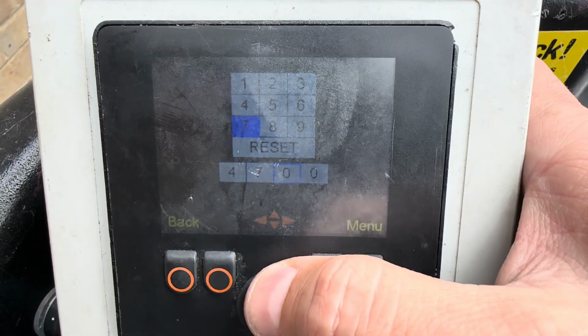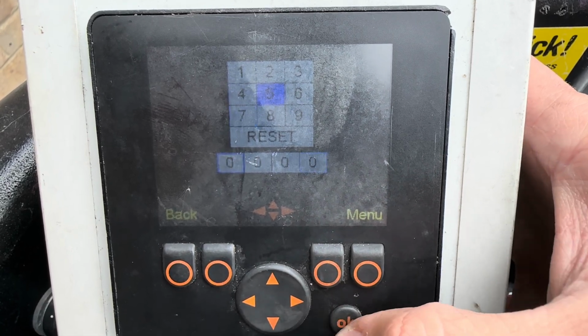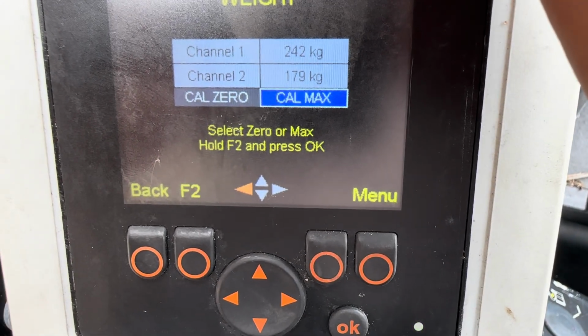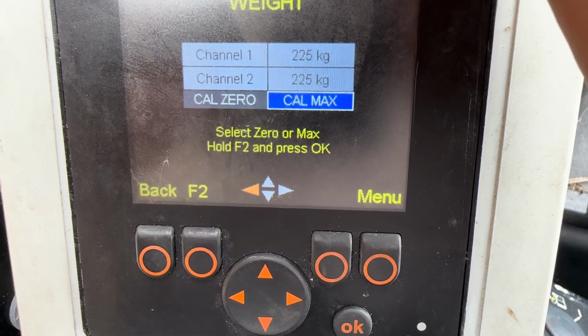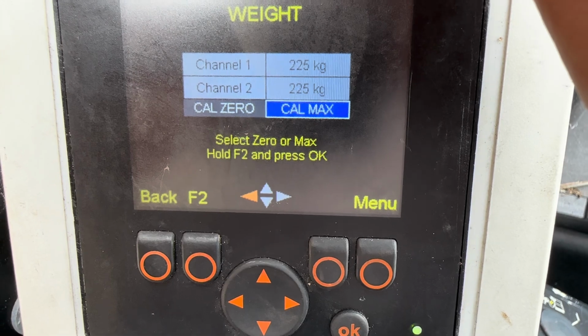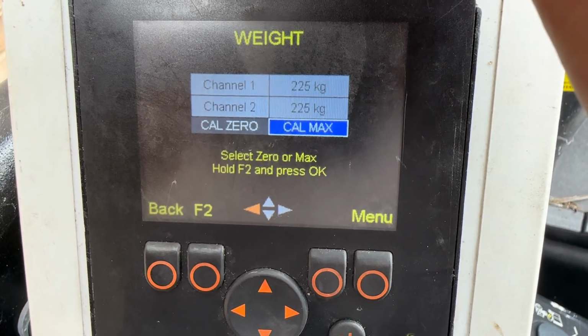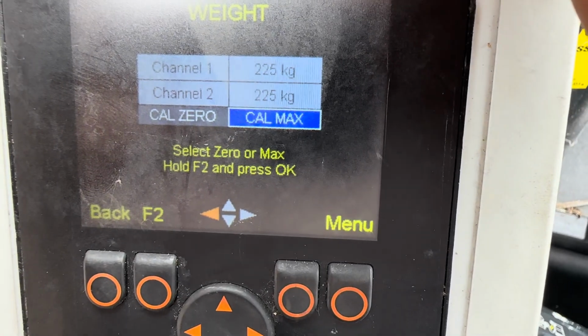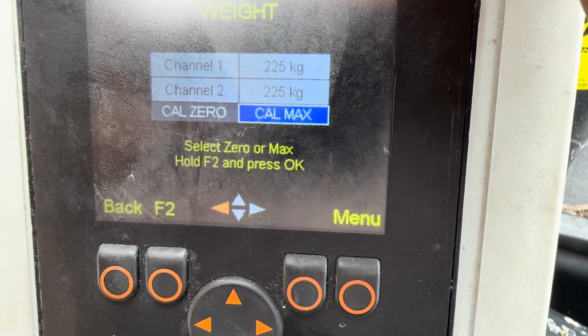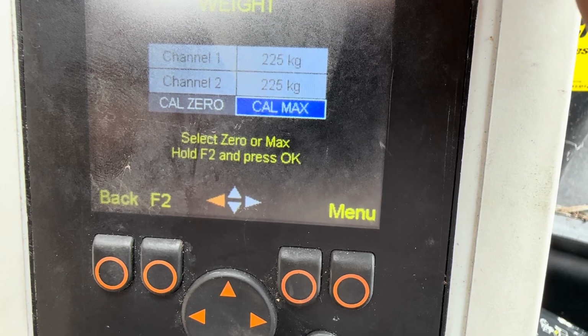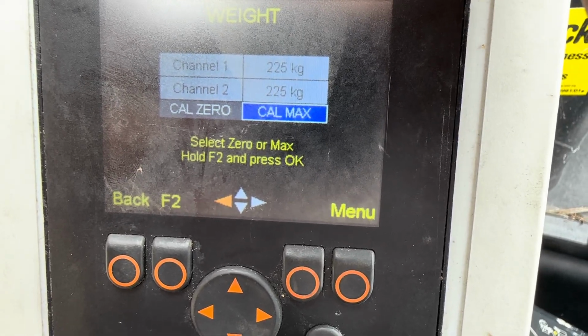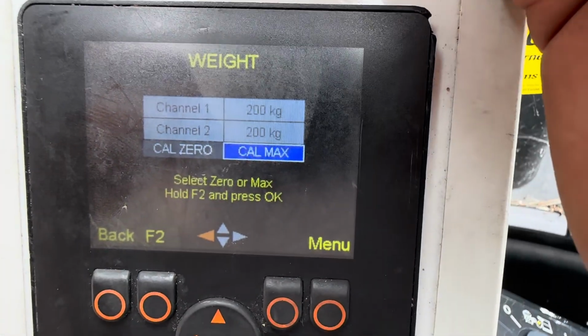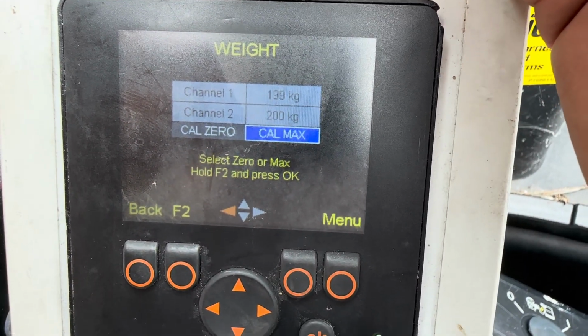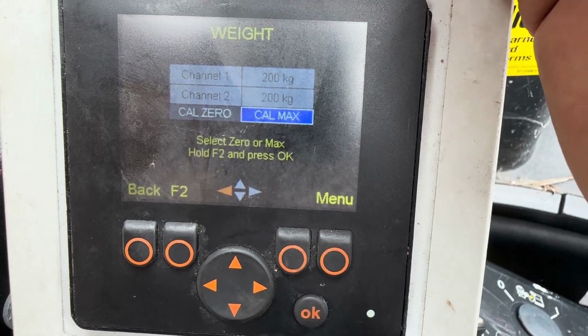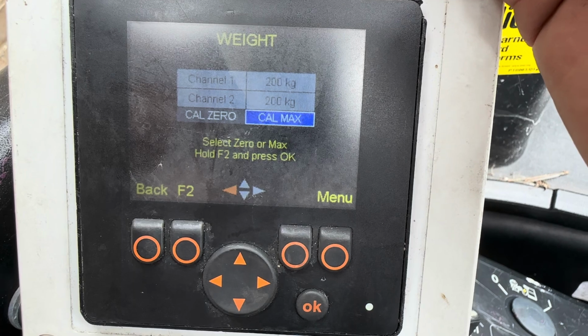So that's done. Now I should take some weight out and I should see 200 kilos, I think. I will take the 25 out, and it should be 200 kilos in the basket, and the alarm should stop. Okay, so I took 25 kilos out, and it's reading 200 kilograms. The alarm has stopped, and that's just perfect on both channels.